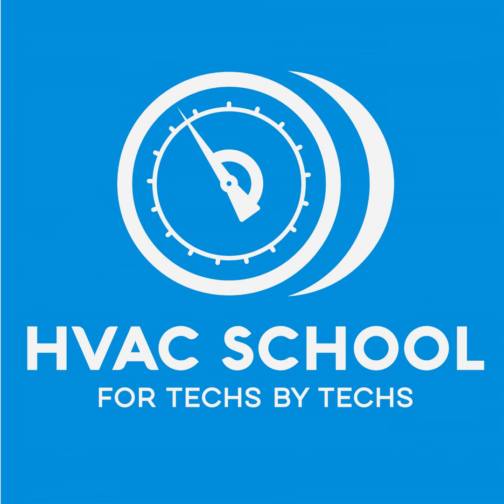Most VRF system manufacturers, as far as I know, are switched or are using a PVE oil. Actually, we've had some really good conversations lately about this and the characteristics of PVE oil. But we're talking about where if you don't get that evacuated and dehydrated correctly, you can run into issues with sludging up and changing the viscosity of your oil. I would absolutely say your nitrogen purging, your evacuation, and being really thorough with your control wiring are the three big things when it comes to VRV installations and the longevity and the reliability.